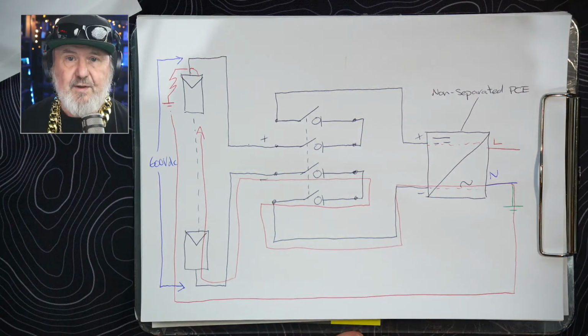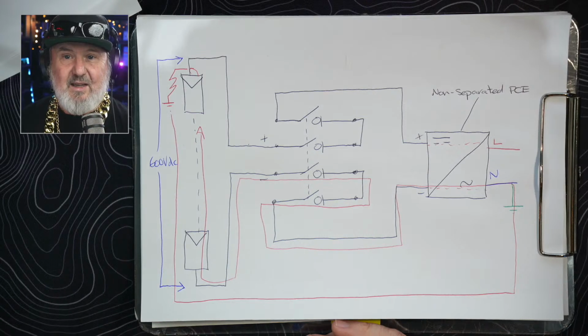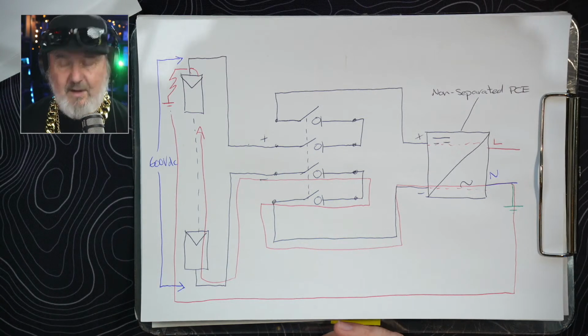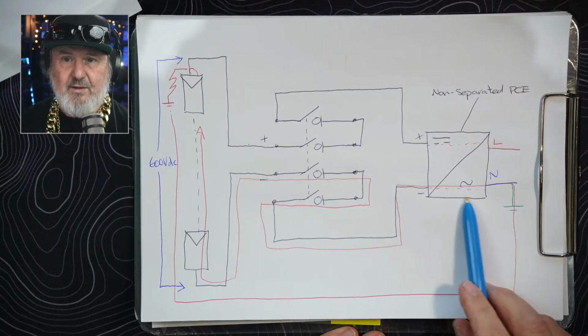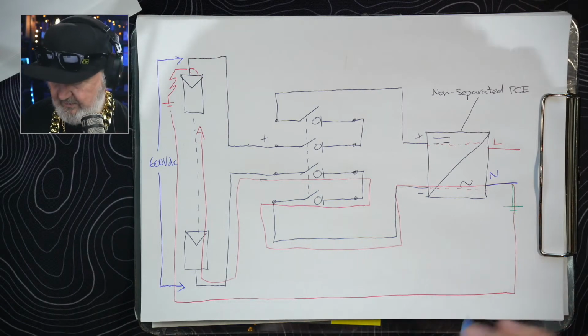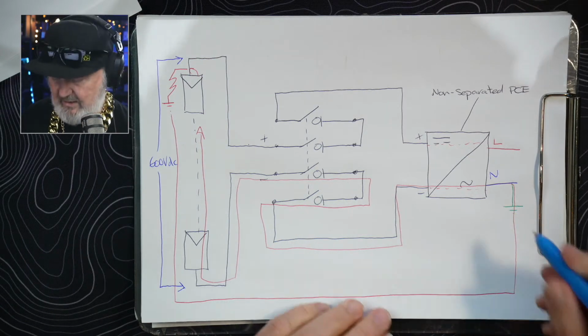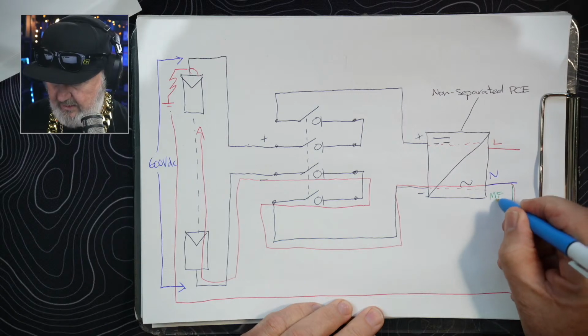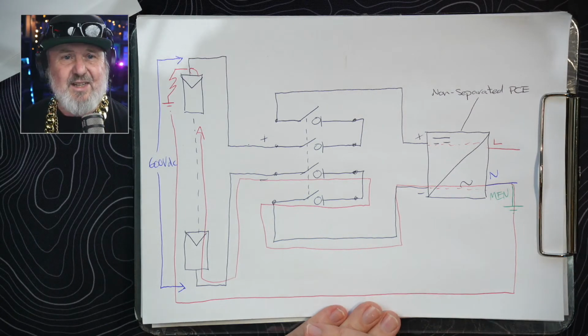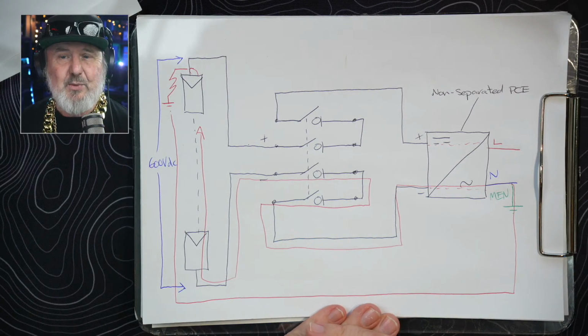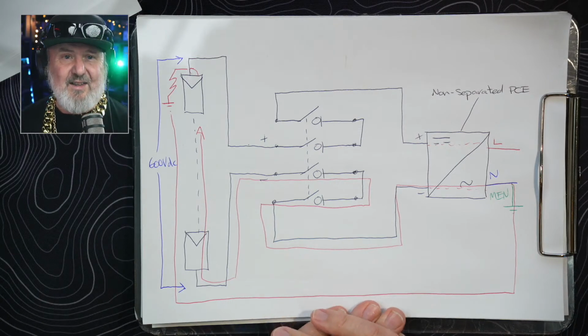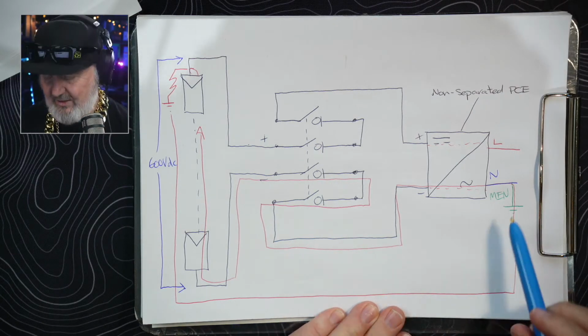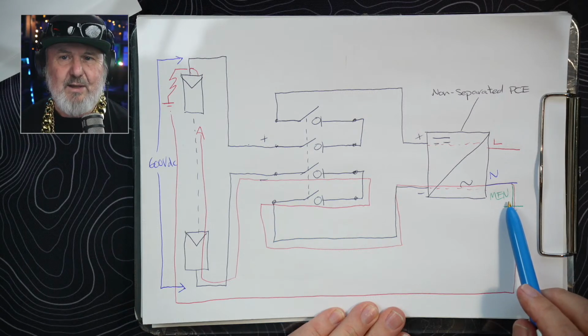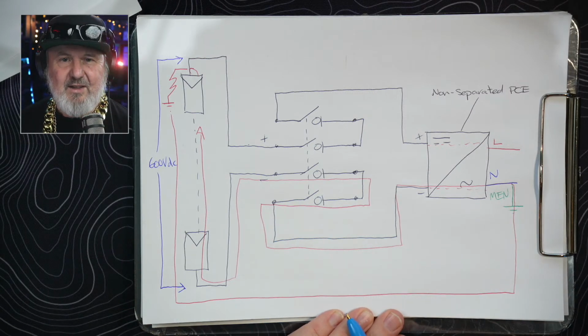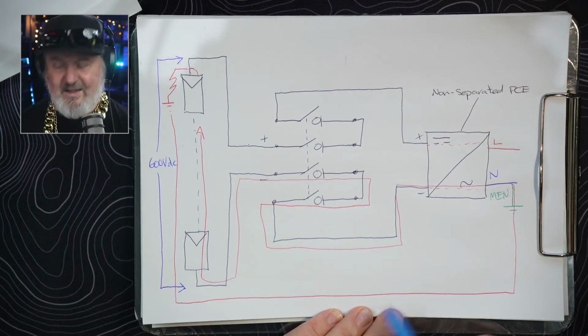So we now have a fault through the system, not only through the PV array, it's going through the inverter, it's going through the MEN. So for those who are not familiar with Australian and New Zealand standards, we're technically known as a TNCS earthing system, which means we bond the neutral conductor at the main switchboard to earth, and we call that a main earth neutral, or MEN. So under this situation, this fault, I need to remove the inverter because it's dead.